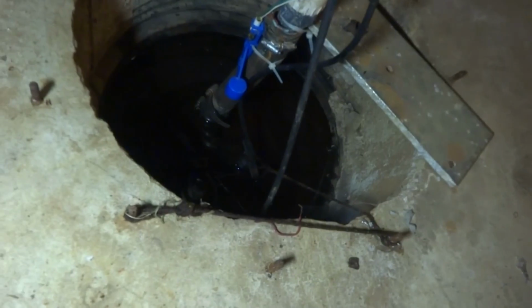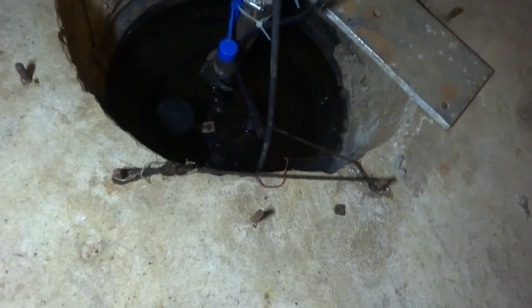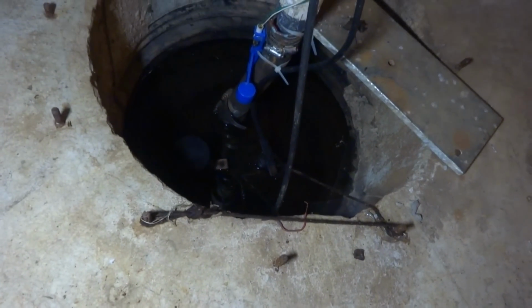You said this is the one that was smoking? Yeah, I'll put a brand new pump in there. The breaker for it was tripping the panel. When I restarted it, it started humming, then smoke bubbled out of it and smelled horrible. I just unplugged it, the cord started getting hot. Yeah, we don't want that.